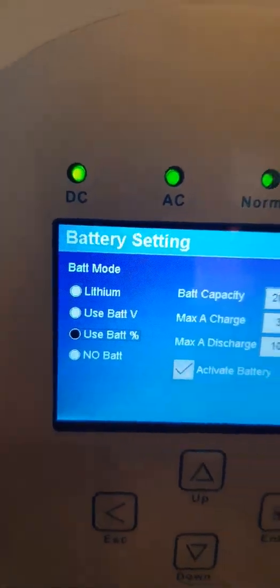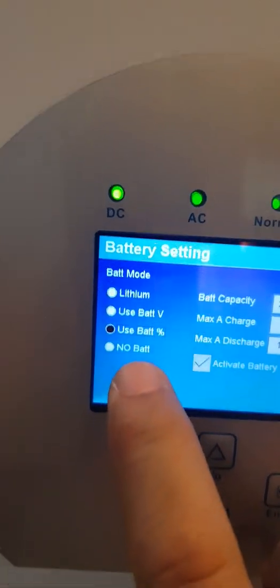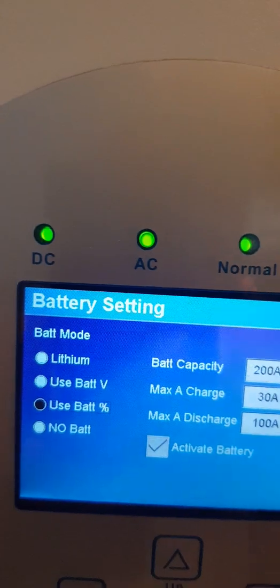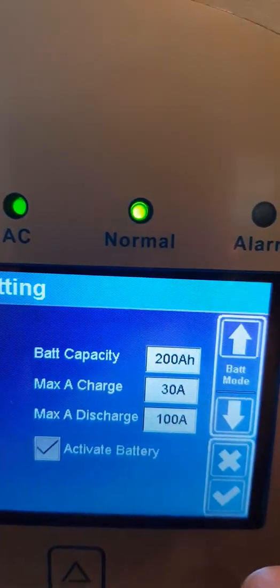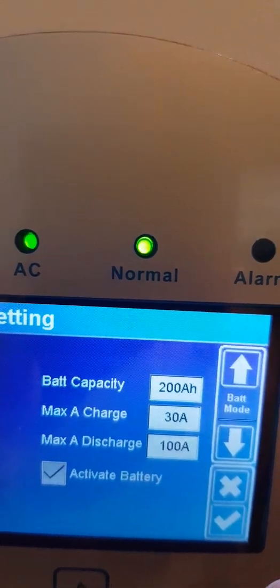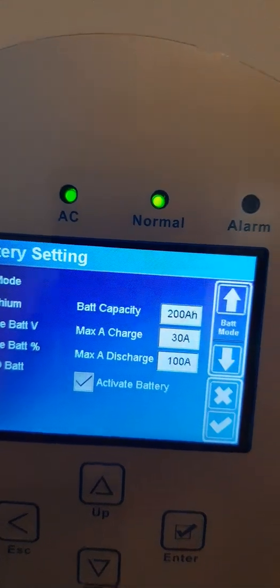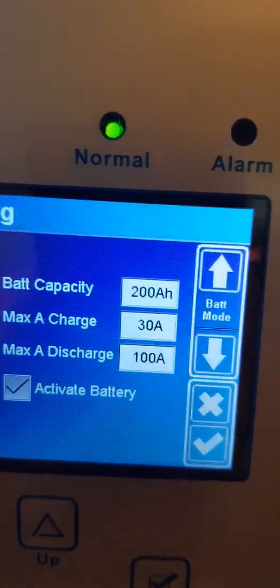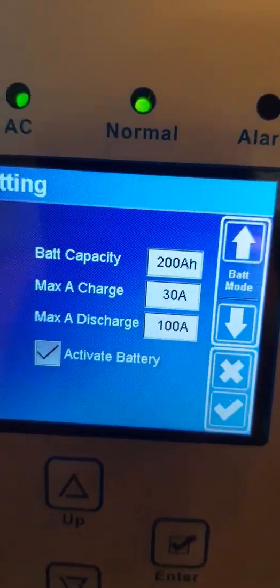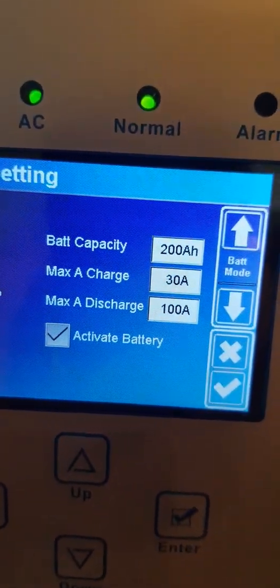So if you have a GSL battery or other batteries with communication ports, we will choose the lithium. But right now, since these power walls have no communication ports, that's why we use the battery percentage. Currently, it's set to charge at 30 amperes. Battery capacity, since these are both 100 amperes each, the total you will use for parallel connection is times 2, so total is 200 ampere hours. Maximum charge is 30 amperes. Maximum discharge continuous is 100 amperes. So next page.